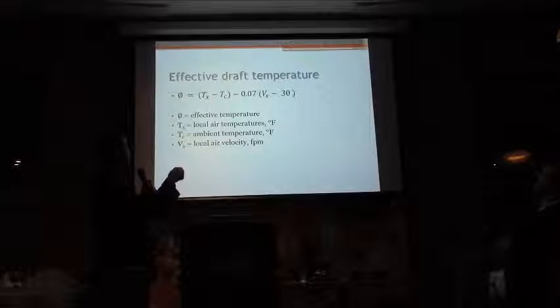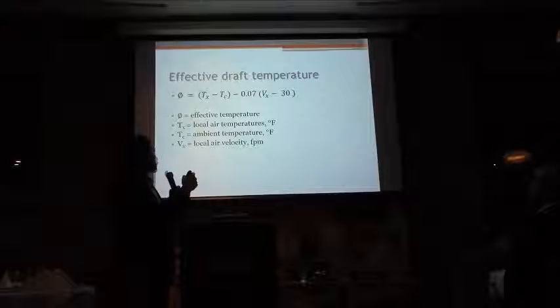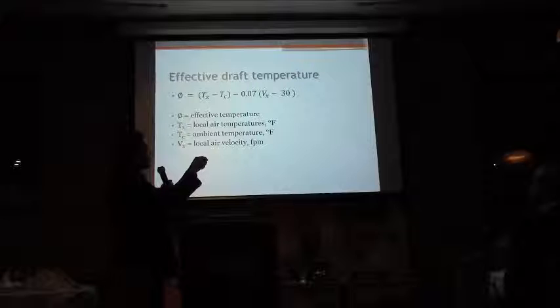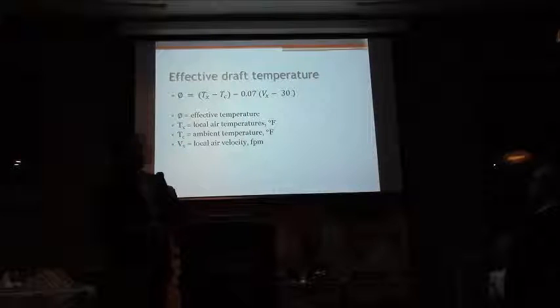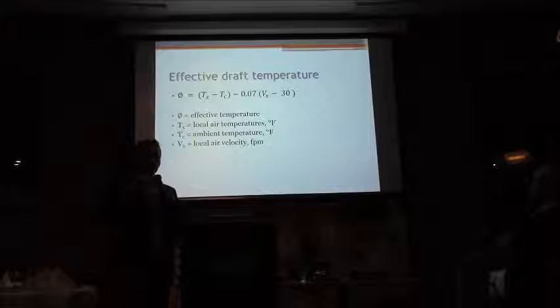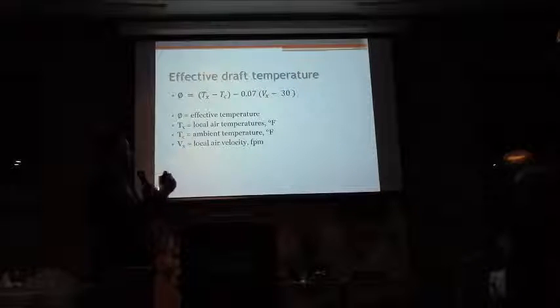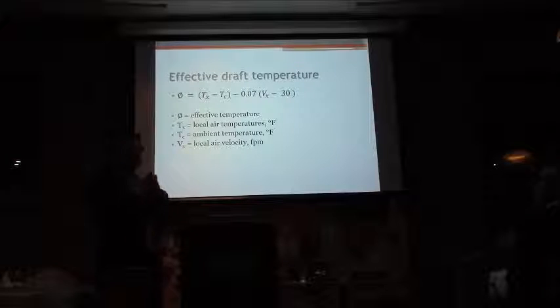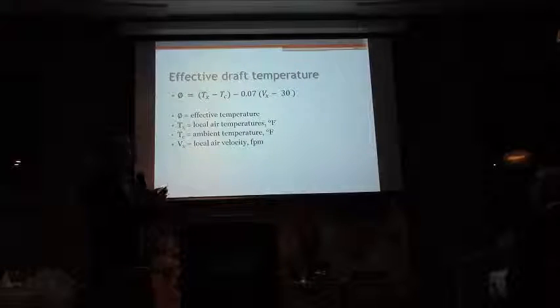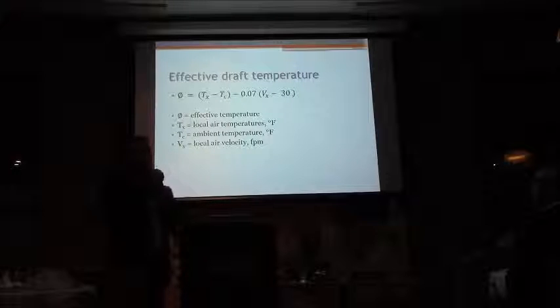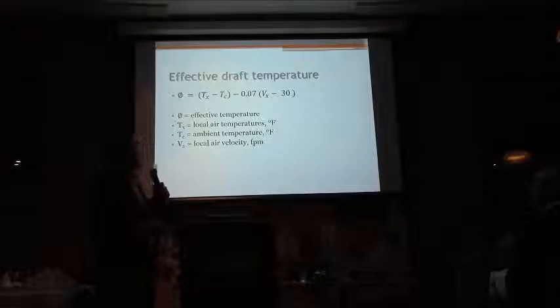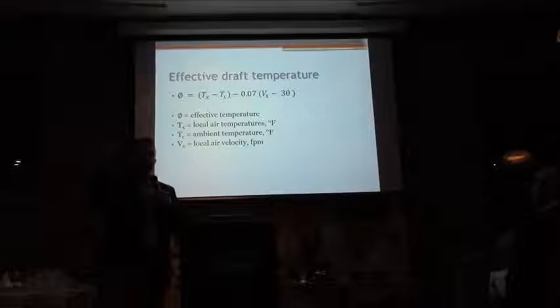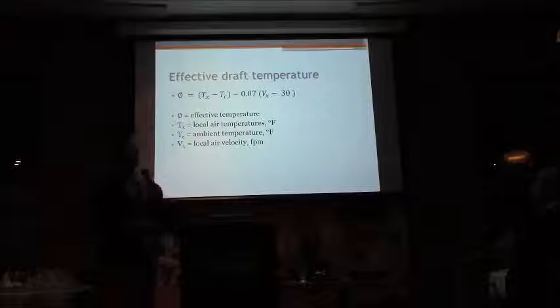Because if, for example, your set point Tc is at, let's say, 72, and Tx in cooling mode, you measure it at 71. So 71 minus 72, that's minus 1. Any velocity over 30 is going to reduce your effective draft temperature. So it's just to say that any velocity over 30 is going to contribute to the effect of coolness, and that's true in cooling and in heating mode. If you do it the other way around, if your set point is 72 and you measure 73, well, the effective draft temperature is going to always go down with velocities higher than 30 feet per minute. So I mentioned you want to have a maximum velocity of 50. That's good, but if you want to go even better, 30 is the maximum velocity.